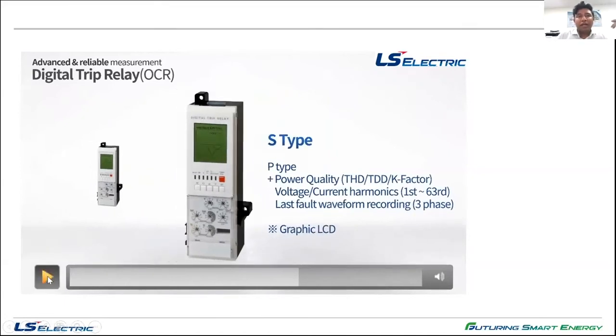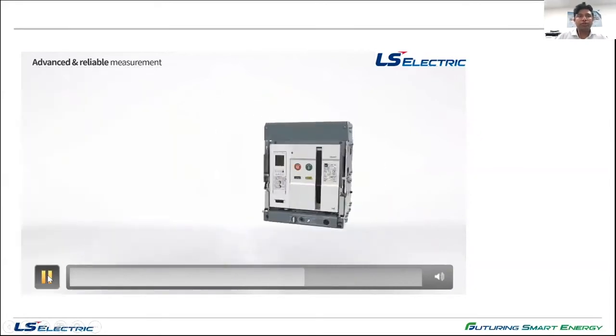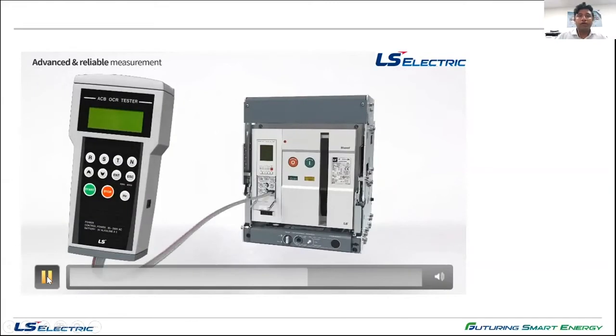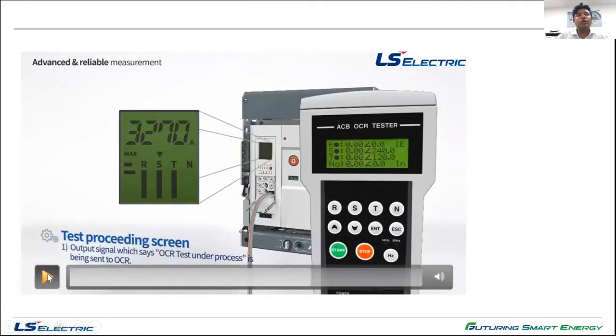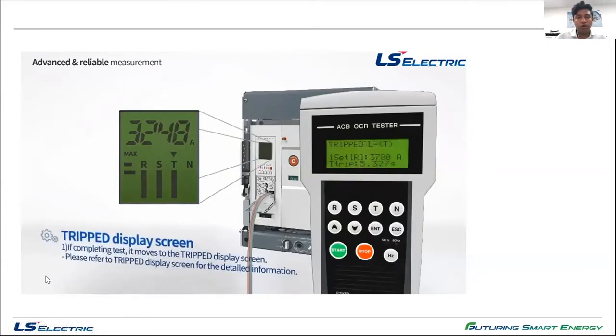And finally, we have the S type. In S type, as you can see, all the functions of P type are there, plus power quality, total harmonic distortion, etc. added in the S type. So these are the different types of trip units that we are offering. We also have an OCR Tester, which can normally be used for a factory acceptance test if you want to show your consultant the different tripping times, etc., and make sure that the ACB is working properly. You can buy an OCR Tester and keep it, and it will connect to all our digital trip relays for all the frame sizes.